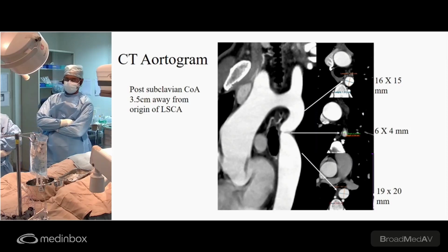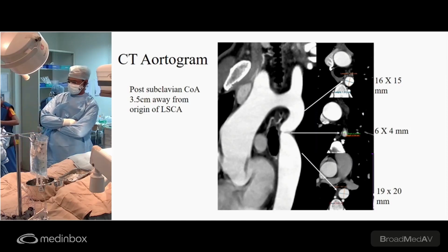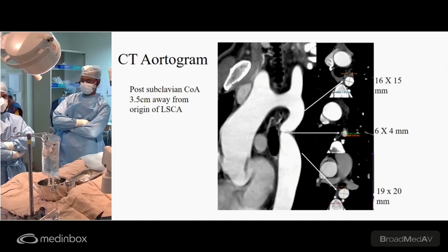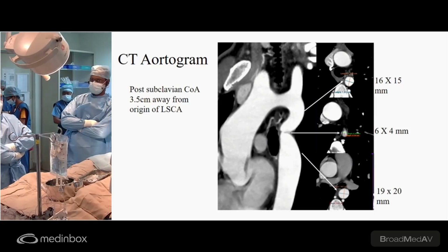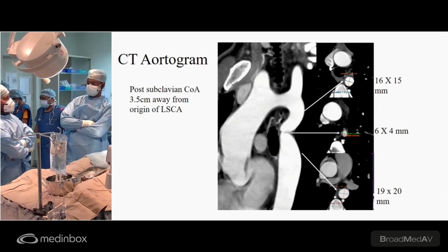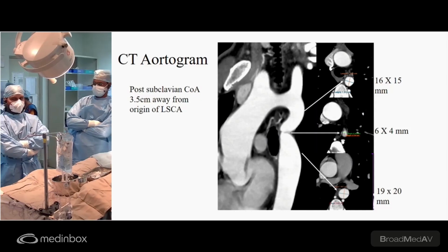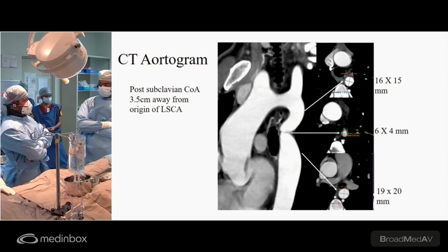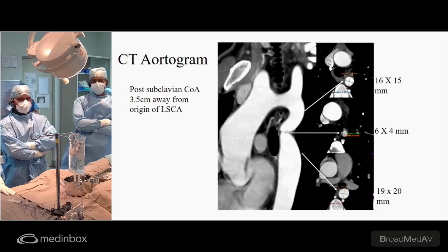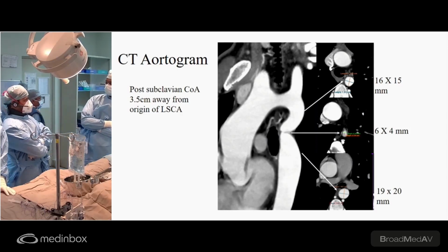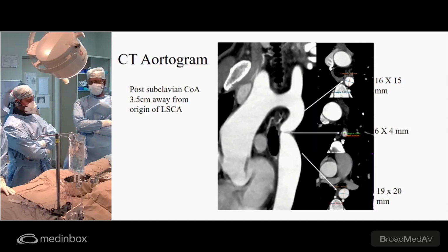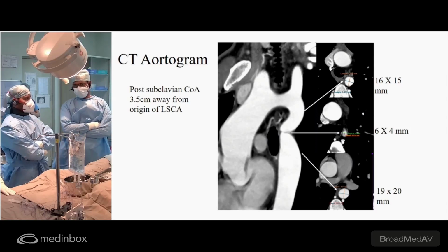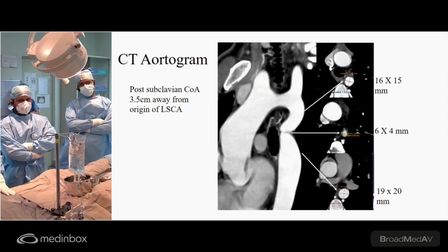The main advantage that I feel in this case is the sheath size. If you are planning a 16 millimeter diameter and want to use a covered stent, at least a 12 French sheath is required, whereas with the bare metal we can go with 11 or even 10. We can cut down the vascular access by 1 to 2 French if it is a bare metal stent. Yes, sir. And so let us do one thing.